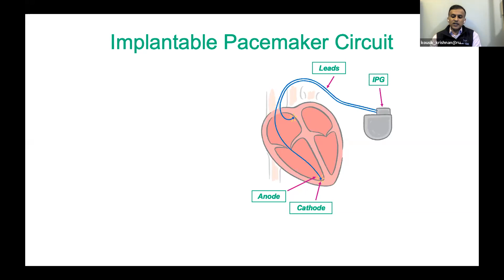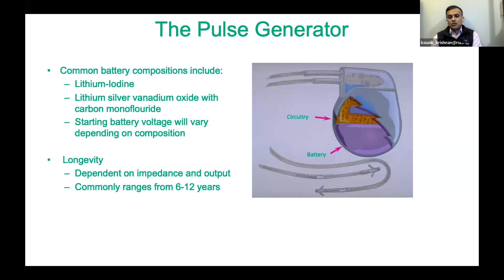The batteries, depending on which company, have different compositions, but they're often some variant of lithium, lithium iodine, lithium vanadium, and they have a very slow but predictable decline over time and can last upwards of 10+ years in today's iterations of these devices. The longevity of the battery is going to be determined by other factors, not just the natural decay of the battery, but how much current is drawn, and that will be determined by the capture output and how often it needs to pace. A patient that may pace 100% of the time will obviously use up more energy per day than someone who paces 1% of the time. And those are all factors that will contribute to longevity.